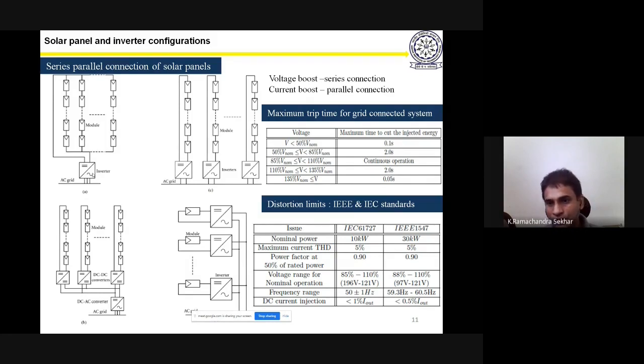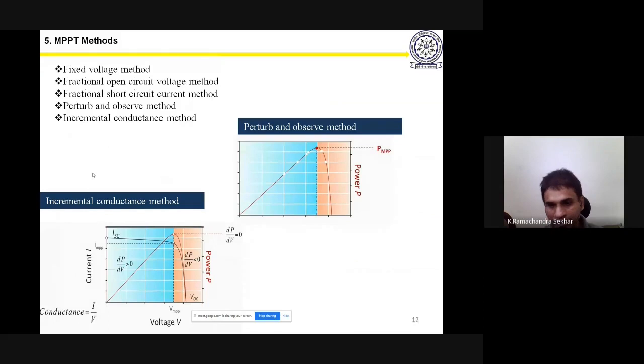So that's all I mentioned. What are the distortion limits and IEC standards, I think we have covered already. This is the MPP point. We have different algorithms to track the maximum power. Here, if you see, the current is fixed, even though if you increase the voltage, power increases, up to a certain extent. After that, it will fall based on the characteristics. After the MPP point, the current will fall drastically if you increase the voltage further.